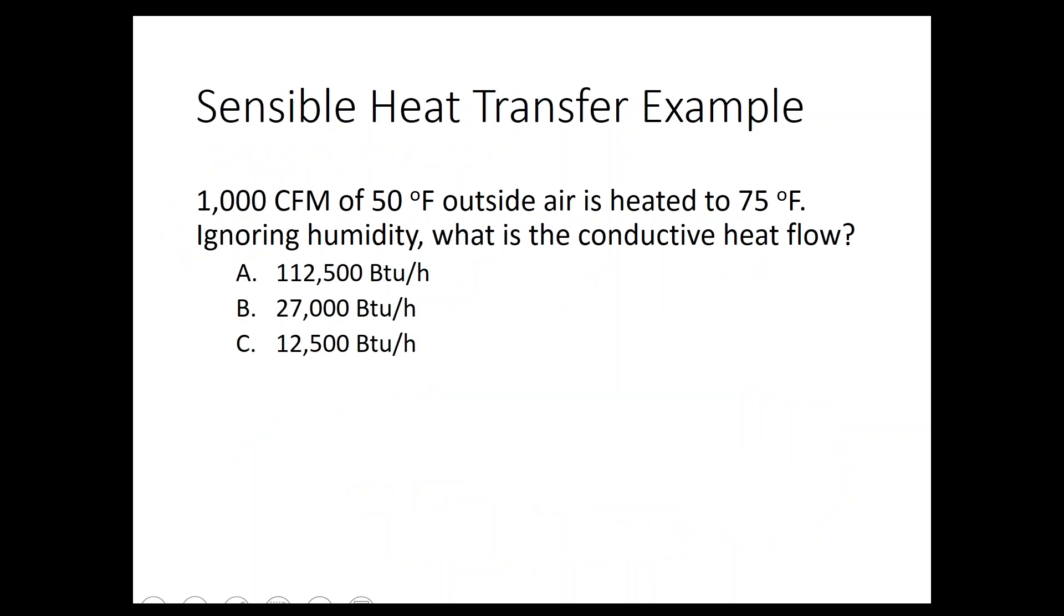Now if you've done this before, maybe you want to quiz yourself, just pause the recording right here, see if you can solve this problem. So this is an example, you got 1000 cubic feet per minute of 50 degree outside air, and then you heat that up to 75 degrees. And ignoring humidity, what's the conductive heat flow? So we're going to use the equation on the previous slide. Q equals 1.08 times CFM times delta T.